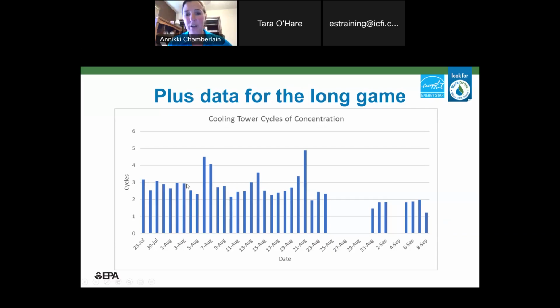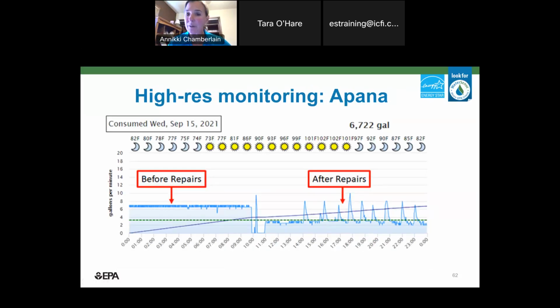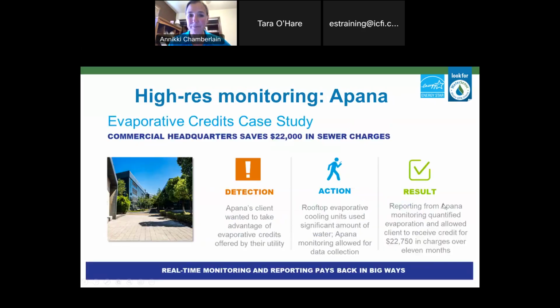These guys are running a little bit less than 3. After that failure, it dropped down to about 2, so they know they need to get that back up. Here's another example of Apana data. Here's a constant flow of makeup. Boom, stuck wide open. They do the repair, and then boom, we're back to our normal makeup pattern.